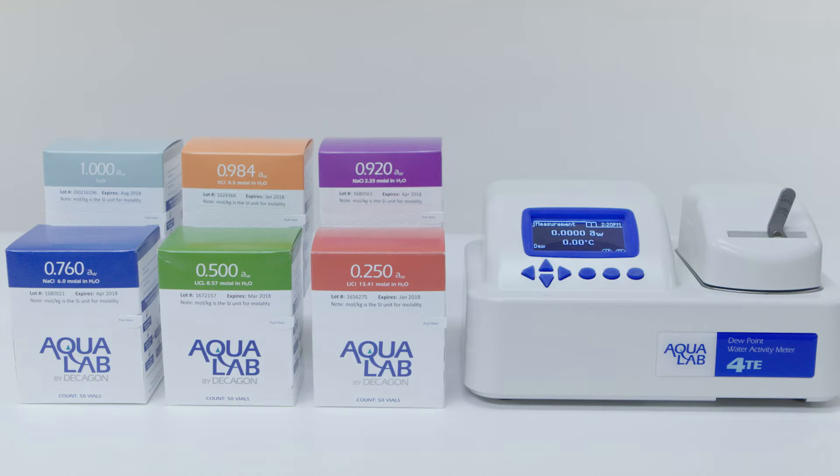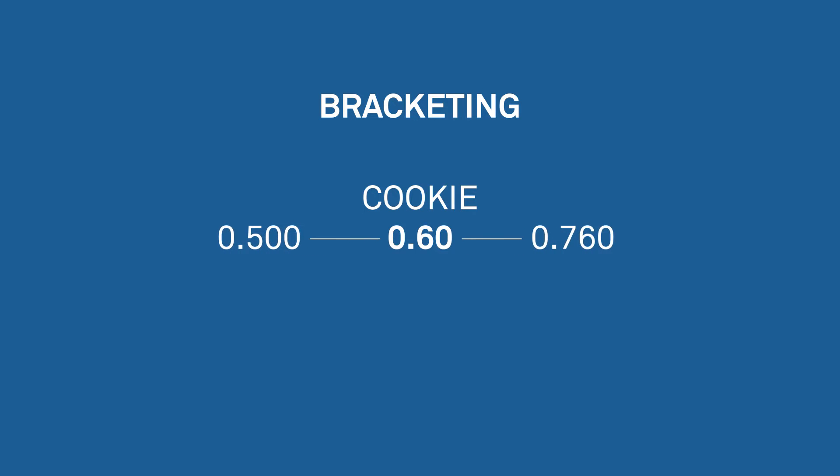The best way to verify your instrument is to use a technique we call bracketing. If you are measuring a cookie that typically has a water activity of 0.60, you should use the 0.500 and 0.760 standards to verify. If you are measuring milk powder in the 0.3 range, you should use the 0.250 and 0.500 standards to verify.